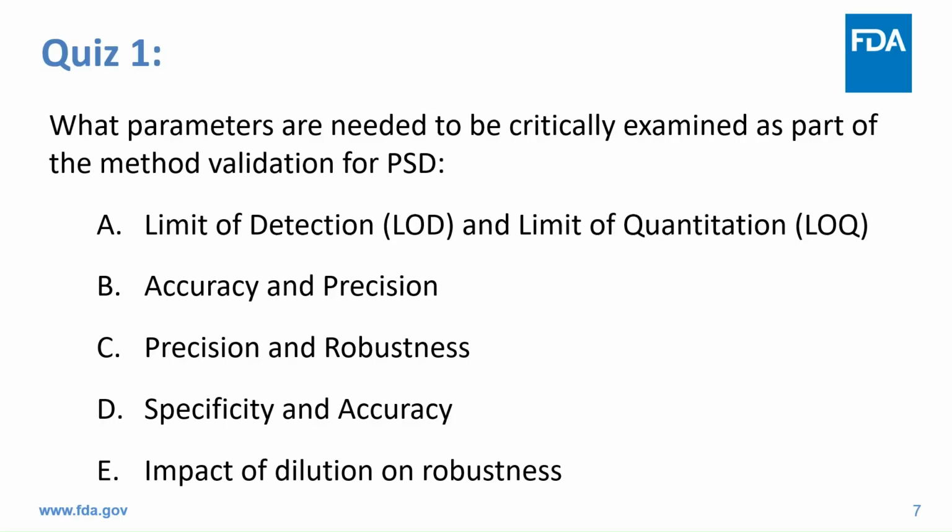Robustness, again, is really important, and robustness can take different forms. What you consider as robust might be temperature, stirring speed, amount of sample added, the position of the sensor, the effect of procedure, diluting. All of that, what we want to make sure is that the company actually knows what they are doing, and that what they are doing is not going to cause misleading results, right?